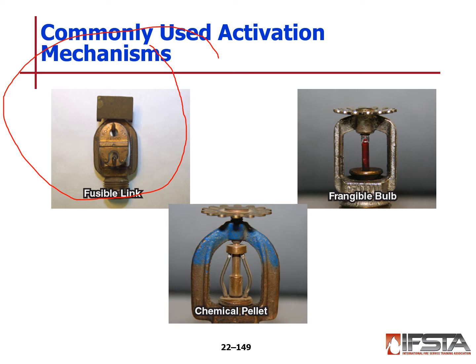On the top right, with your liquid filled glass bulb, once this liquid heats to a certain temperature, it expands to the point where it will overcome and break the glass. Then the base, because it's under pressure, will fly apart and water will begin to flow up against the deflector. And then on the bottom is the chemical pellet. At the very top of that you see your pellet, and everything's fused together. Again, when this meets a certain temperature, it degrades and comes apart, and then the base will come up off of there because it is under a little bit of water pressure, and then the water flows and deflects off the head.